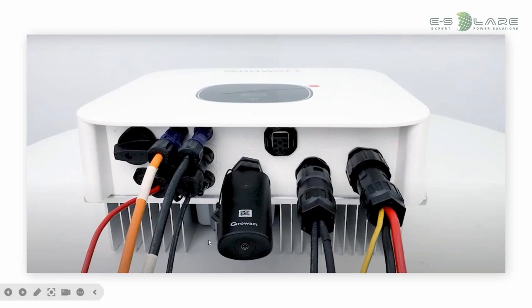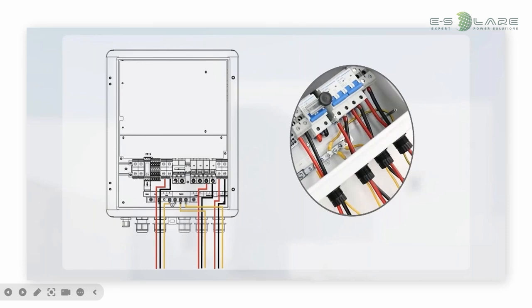This picture shows the installation, connecting to AC and communication. This one is a dongle and battery terminal and PV. This is as well. And one thing you need to notice is to make sure you turn off this breaker during installation.